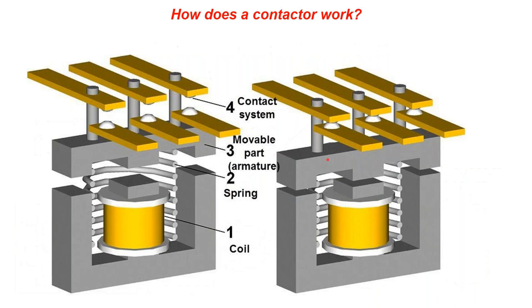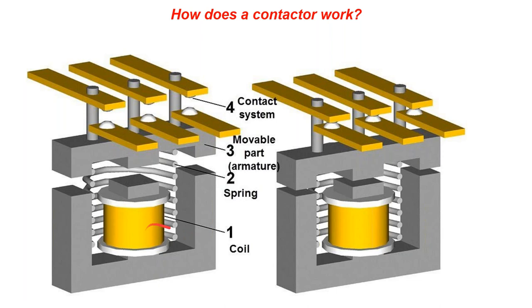The contactor itself: when I first got into controls, someone took a contactor apart and explained how it worked. We have a coil — when we send a signal to energize it, the coil creates an electromagnetic field, which pulls in the armature. As a result, three-phase power is now able to turn on a three-phase motor. I have some videos to show this.